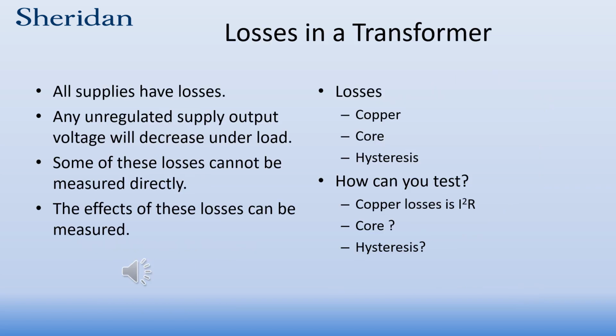Okay, as with all supplies, there are losses. There are internal losses in the supply. Any unregulated supply output voltage will decrease under load. That is to say that as soon as I start drawing current from that supply, its terminal voltage will drop. Some of these losses can't be measured directly. We can't directly measure hysteresis losses or core losses. We could measure copper losses if we know the resistance and the current that's flowing in the transformer.